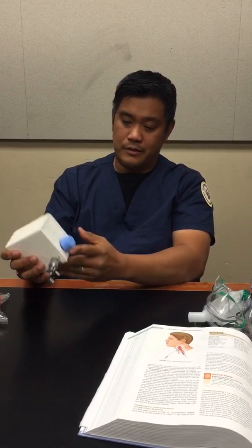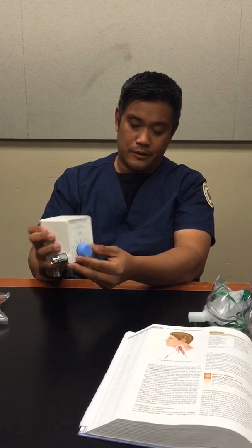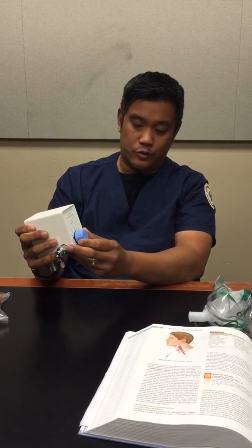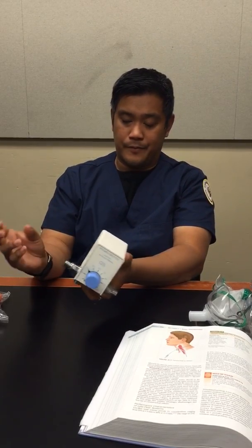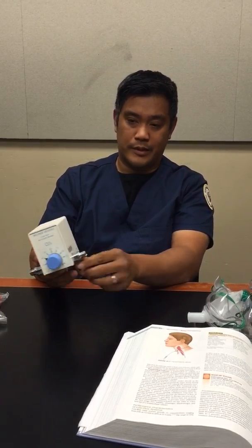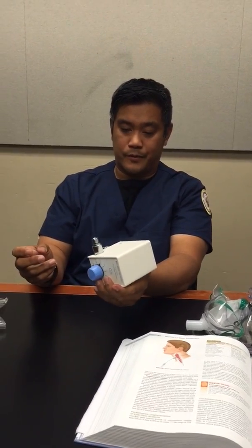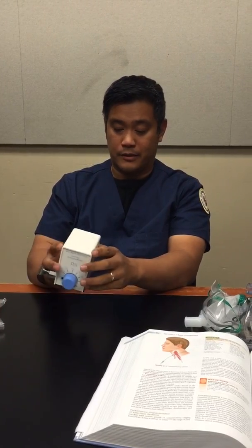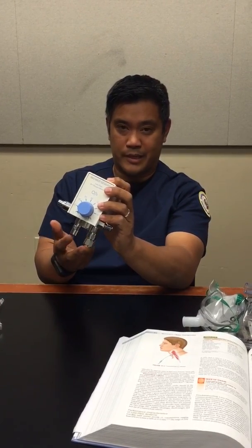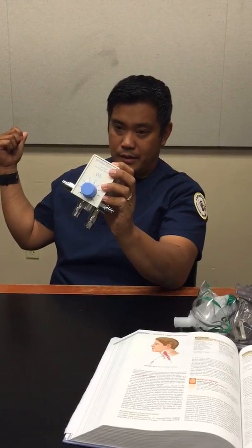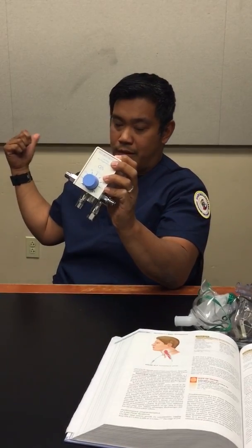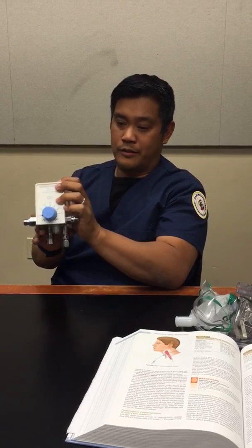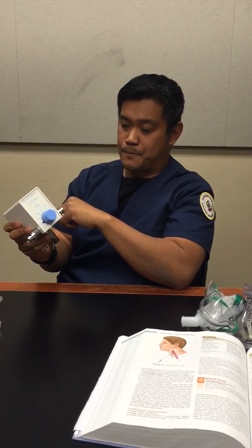So if you look at this device, there is the knob which you can set the FiO2 range as you see fit. Torque tubes would attach to either components, one for oxygen and one for air, medical air. Here is where you're going to be attaching to the wall, to the outlet, the oxygen and your FiO2, and they would blend together and create a high flow for the patient.